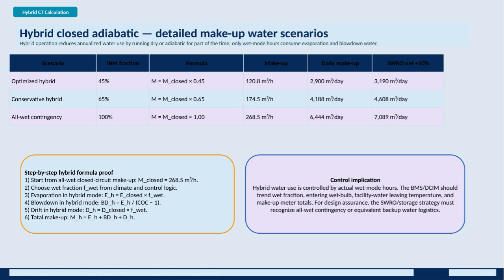Monitoring the wet fraction along with entering wet bulb temperature, facility water exit temperature, and makeup water meters in the building management or data center infrastructure management systems is essential. For design and risk management, the system must account for full water demand in an all-wet contingency scenario or have equivalent backup water supply strategies in place.